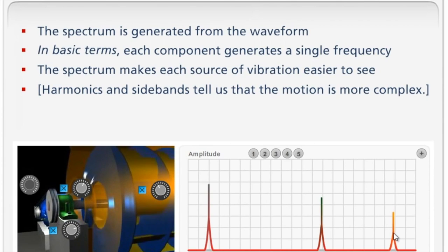So if someone talks about vibration frequency, you might hear them say, oh it was the 10x peak. What's the 10x peak? Well the 10x peak is 10 times the running speed. And a vibration analyst might think, oh I wonder if there were 10 blades in that fan, or 10 vanes in that pump. That's the sort of thing.